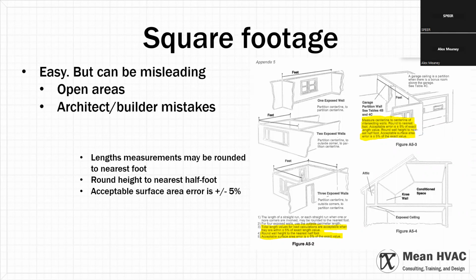If you are going to introduce supply air to the middle of the space and the top of the space, or the top and the bottom, if you're going to do it at 2 levels, you need 2 rooms to do that. So it's going to count square footage of that room that you've added, and that will cause a discrepancy between the builder's plan square footage and the printed square footage. It's a very common sticking point for the submittal process.